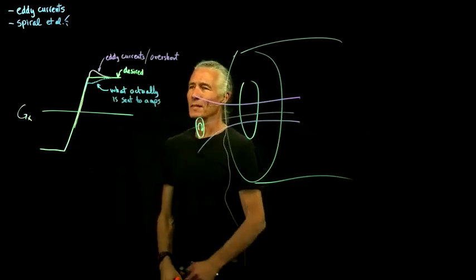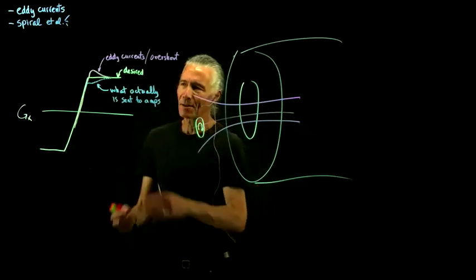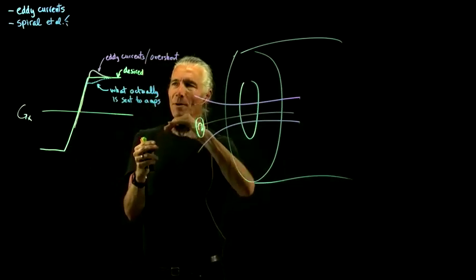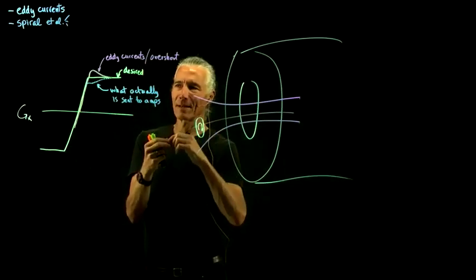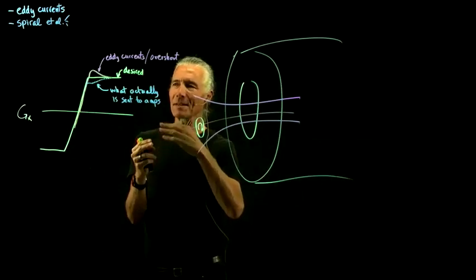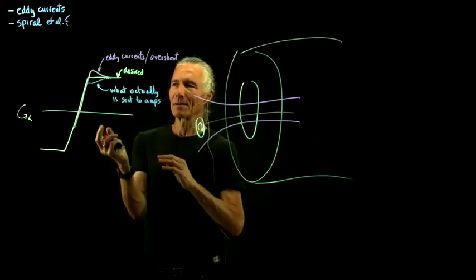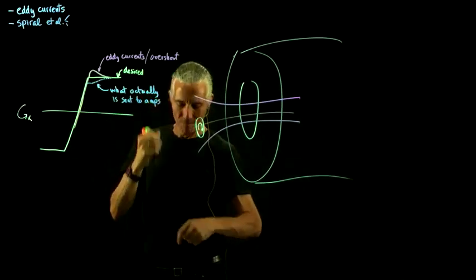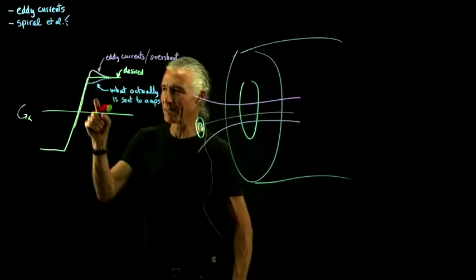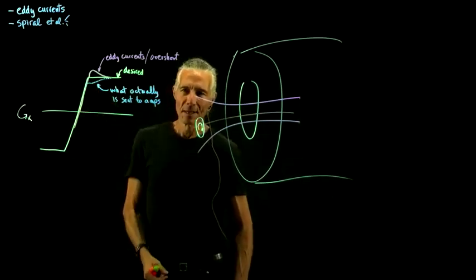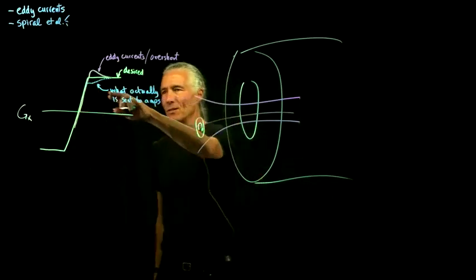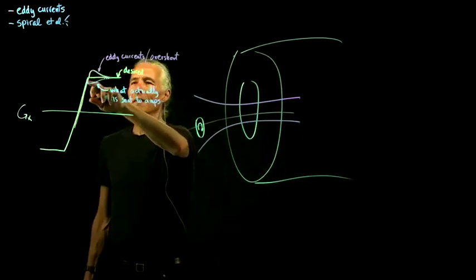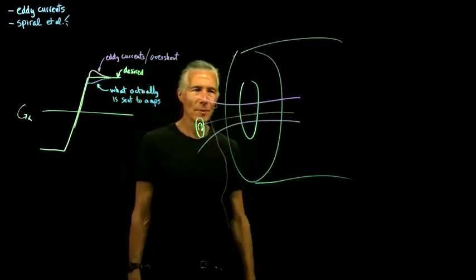And there's various orders of corrections here. It's a complicated thing. You need derivatives and second derivatives because characterizing how the eddy currents actually behave is not straightforward. And so there's hours of calibration to try to guarantee that you get something that actually looks like one of those sharp edges.